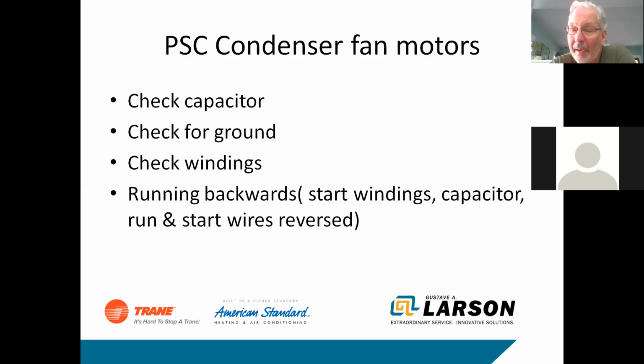If the capacitor is bad, it could start in backwards, or the run and the start wires could be reversed. I've seen that every now and again. Somebody will put a motor in and get the run and the start mixed up, and it'll run backwards. So on the condenser fan motors, just make sure the wiring's correct, the capacitors are good. Check your windings out. So just a few things to check when you're looking at a condensing unit.